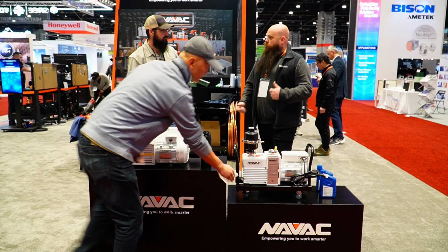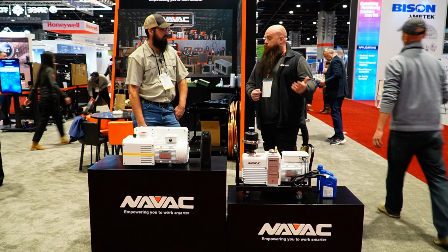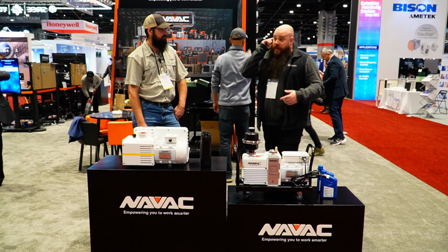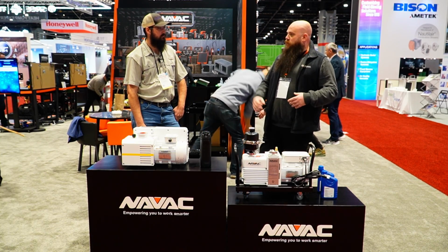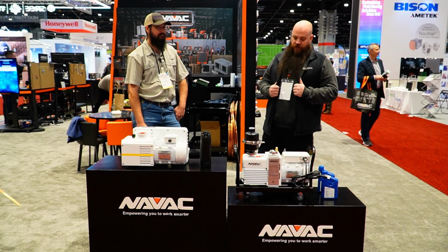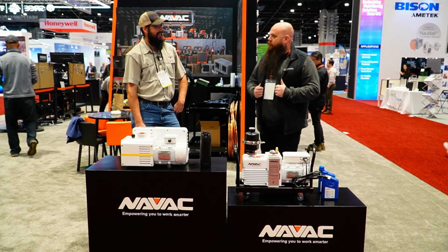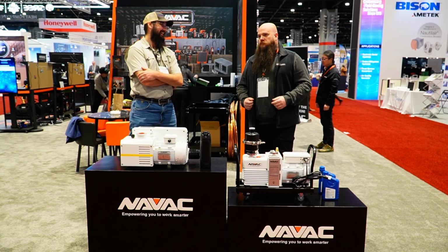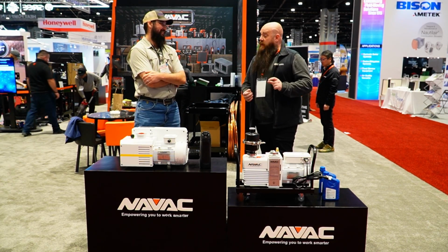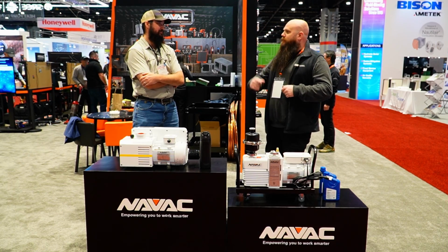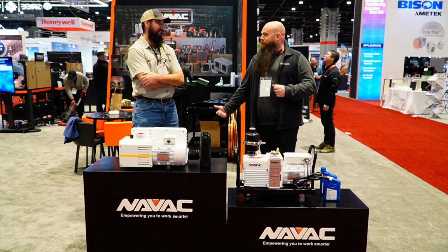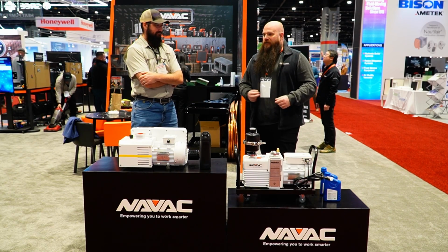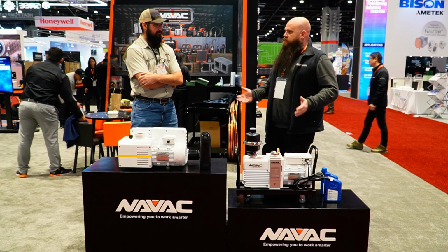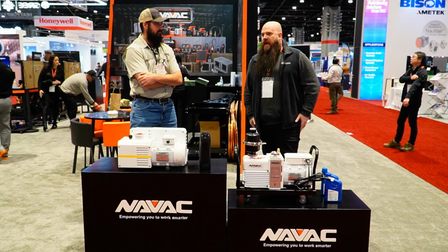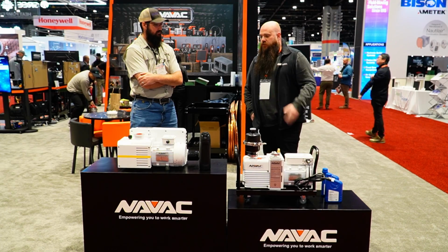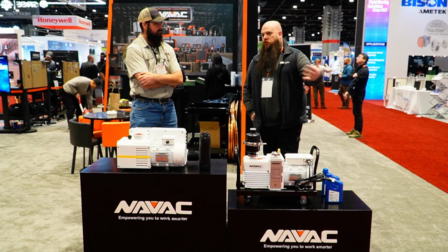Again, the demand at times is for larger CFM ratings. And a lot of that has to do with some of these spec refrigeration jobs. You got Walmarts and, I don't want to throw stones, but sometimes you'll get engineers and these jobs get spec'd out with very specific timelines that they can have the system down offline. They give them 15 minutes to do an evacuation on this massive rack system, and it has to be a minimum of 30 CFM for the pump. There's guidelines like that that really led to us needing to bring some of those more industrial, larger pumps into our side of things.